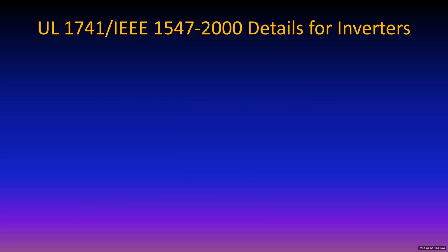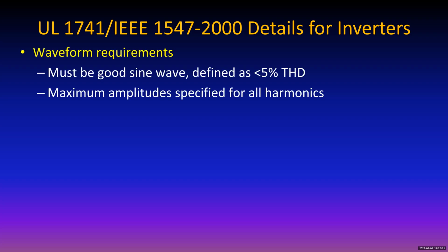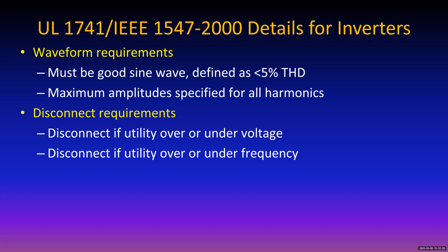it helps to know something about the inverters and what the IEEE 1547-2000 or... Now, IEEE 1547-2000 is a standard. UL 1741 is a test procedure to make sure that the inverter meets the standard as laid down in IEEE 1547. So you see these things used kind of interchangeably. But UL 1741 is the label you want to look for on the inverter. So UL 1741 says you have to have good sine wave, okay? And it says that if the utility goes down, or even if the voltage drops below a certain level or goes under or over the frequency, 60 hertz by a certain level, it has to disconnect. And when it does disconnect, it has to wait 5 minutes before it reconnects again.